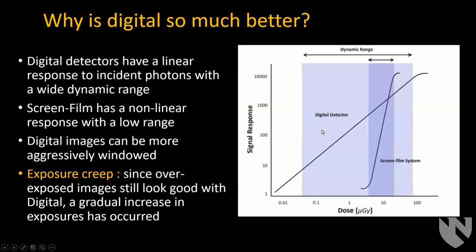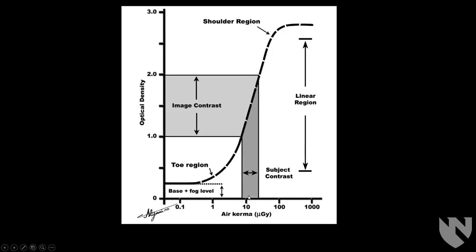The problem with digital systems is that if you give too low a dose, the images will look noisy. But if you give too high a dose, unlike with film where everything looks black, the images will still look good and won't be noisy. This leads to something called exposure creep, where you can end up delivering a higher dose of radiation than necessary while still producing good-looking images on digital systems.